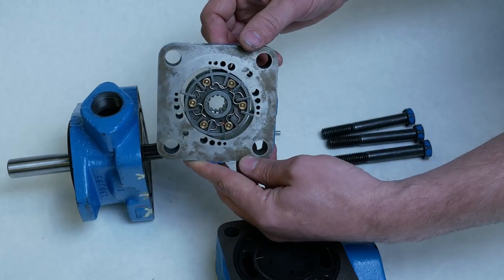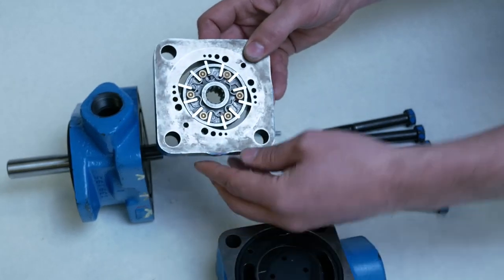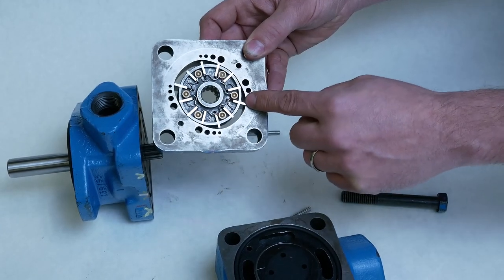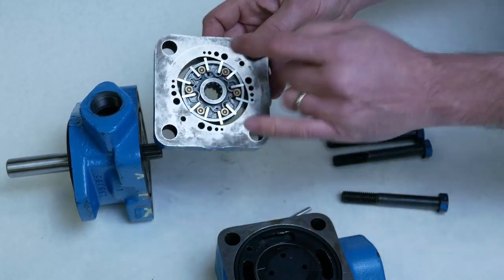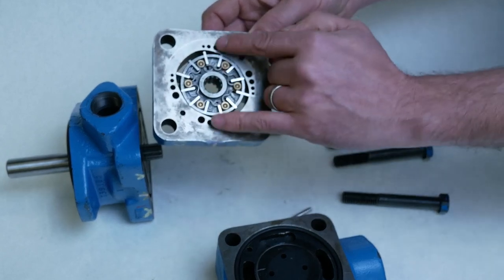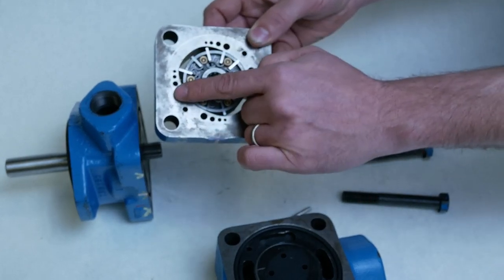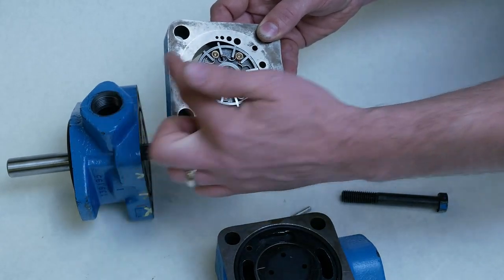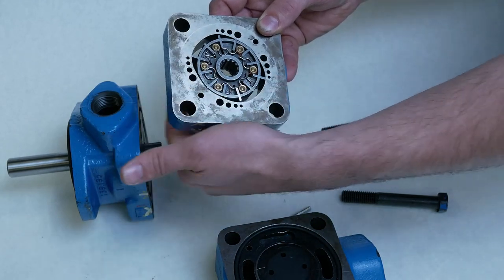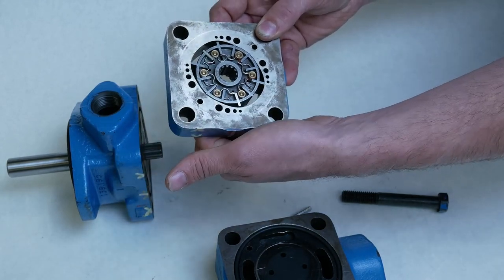We can see that this is a fixed displacement motor. It has an elliptical center housing. And so we have four transfer slots right here. And those four slots are allowed to make sure the oil on either side of the center housing has equal pressure and we don't create any cavitation.